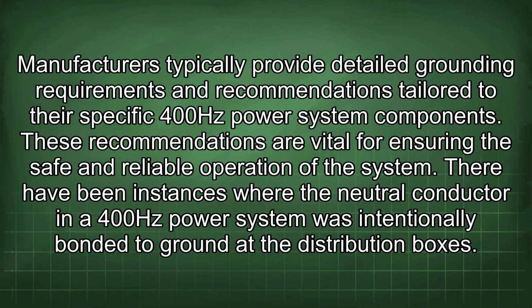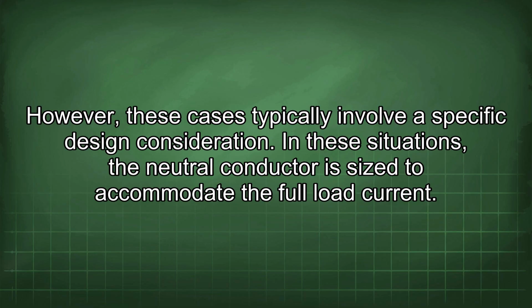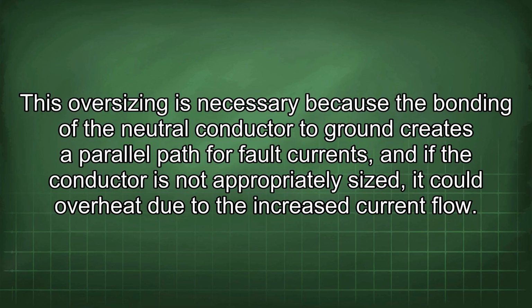There have been instances where the neutral conductor in a 400 Hz power system was intentionally bonded to ground at the distribution boxes. However, these cases typically involve a specific design consideration. In these situations, the neutral conductor is sized to accommodate the full load current. This oversizing is necessary because the bonding of the neutral conductor to ground creates a parallel path for fault currents, and if the conductor is not appropriately sized, it could overheat due to the increased current flow.